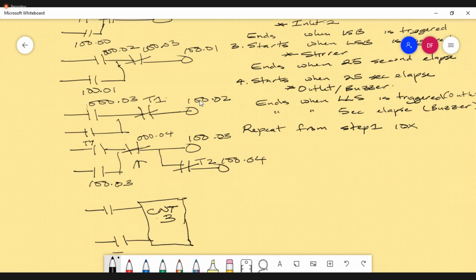So, and it's very important. The program doesn't distinguish between timers and counters. So if you put timer 1 and counter 1 in the program, the program is going to see it as two same things operating very differently. It will be confused and just sit down and look at you. It will indicate that there's an error in the program. It's just going to not function.